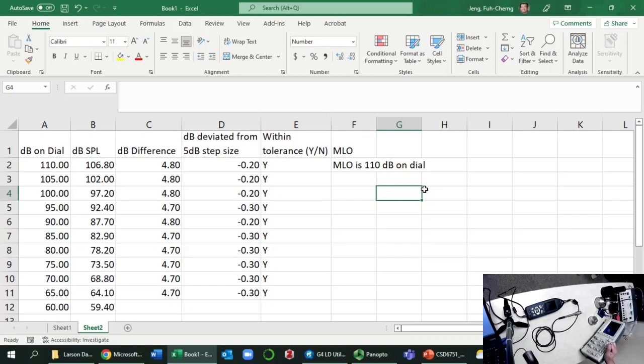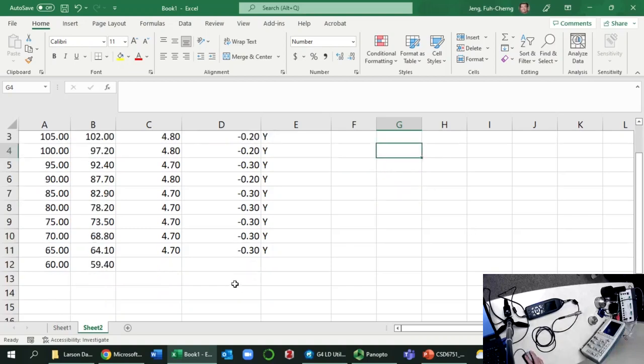Does that make sense? So when you calibrate an audiometer in the clinic, your goal is to make sure it's all within linearity. It should be. Otherwise, it's really broken. Am I making sense? Okay. So we are not going to go to the other end of linearity, which would get down to the very soft sounds. That becomes very tricky because you have to deal with the ambient acoustic noise and the ambient electric noise. Don't mess with that. Okay. Right. So any question about the MLO, which is basically linearity, before I move on to the next measurement? Good. Okay. What is the next measurement?